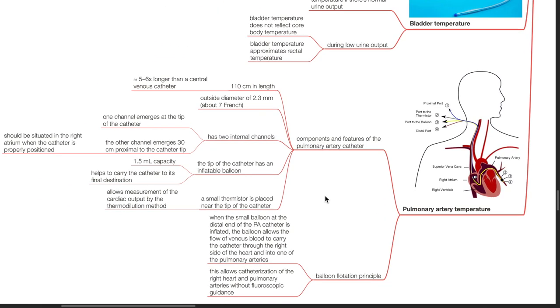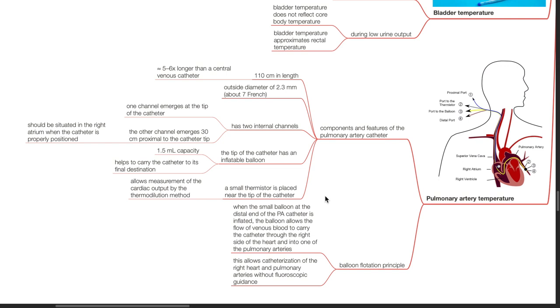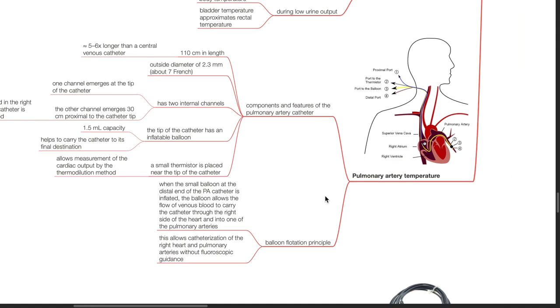Pulmonary artery temperature: the pulmonary artery catheter is 110 cm in length, with an outside diameter of 2.3 mm (about 7 French). It has two internal channels — one emerges at the tip, the other emerges 30 cm proximal to the tip and should be situated in the right atrium when properly positioned. The tip has an inflatable balloon of 1.5 mL capacity that helps carry the catheter to its final destination. A small thermistor placed near the tip allows measurement of cardiac output by the thermodilution method. The balloon flotation principle allows venous blood flow to carry the catheter through the right side of the heart and into one of the pulmonary arteries, enabling catheterization without fluoroscopic guidance.